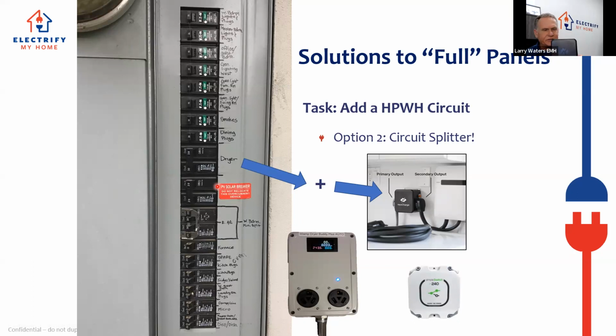What this device does is it allows you to plug it into the dryer outlet. It allows you to plug the dryer in one side, and we use these a lot for heat pump water heaters. So we'll plug the heat pump water heater in the other side. And what happens is one side takes precedence over the other. It gives a little bit of power to run the controls on both appliances, but as soon as one pulls peak load, it shuts off the load to the other side. So with this scenario, we can heat water with our heat pump water heater anytime we're not using the dryer. As soon as the dryer turns on, it takes power, turns it off to the heat pump water heater, dries the clothes, goes back to heating the water. So this is a great solution.